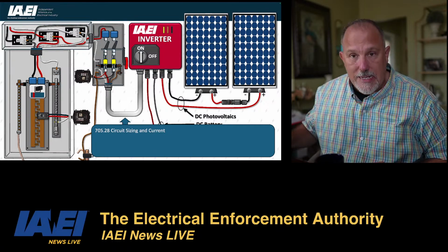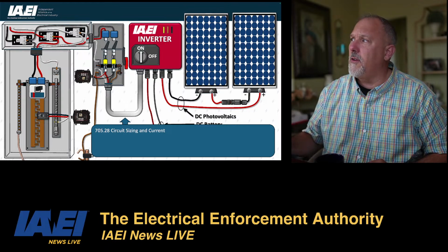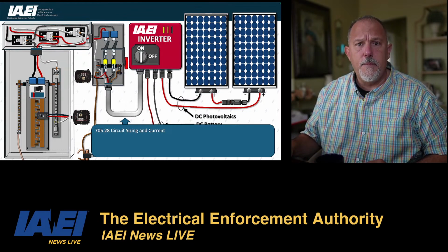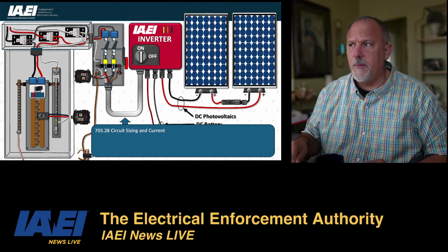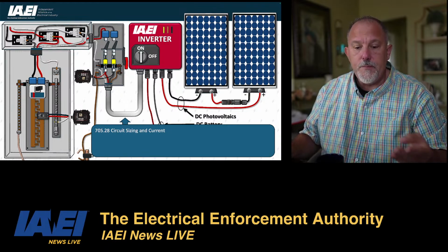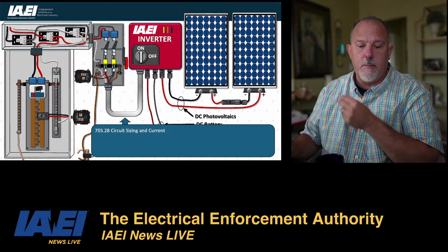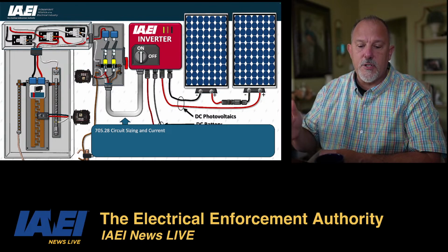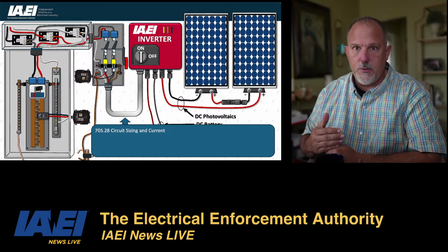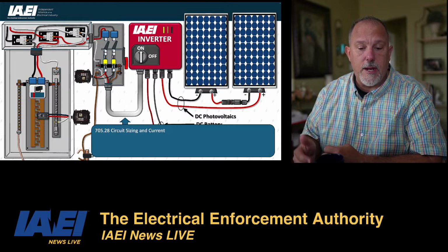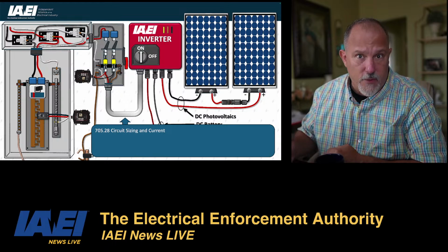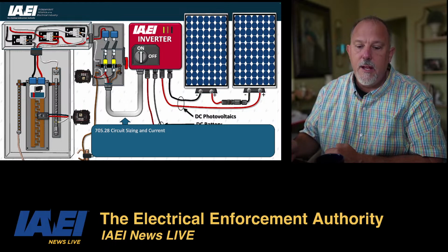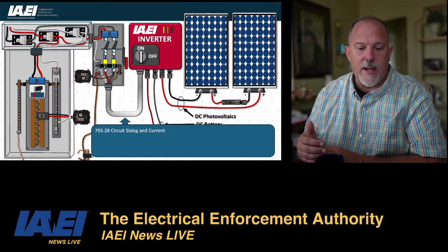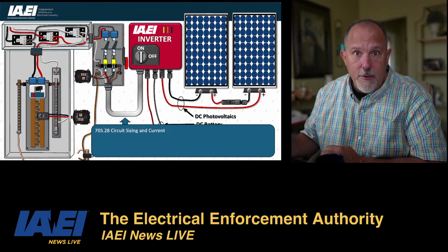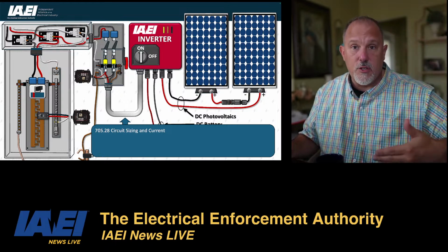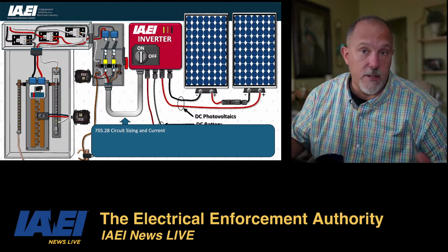And in the 2026 code cycle, it's going to be Article 130 coverage, because that's going to be your energy management systems. And then the third option is where the sources controlled by the energy management system are combined with the other sources on the same power source output circuit. The sum of A1 and A2 is used. So A1 is the sum of continuous output current ratings of the power production equipment at the circuit nominal system voltage. Item 2, I use the setting of the EMS. And item 3 tells us when I have sources that are controlled by EMS combined with other sources, then I add the two options above. I'm sure it's as clear as mud.